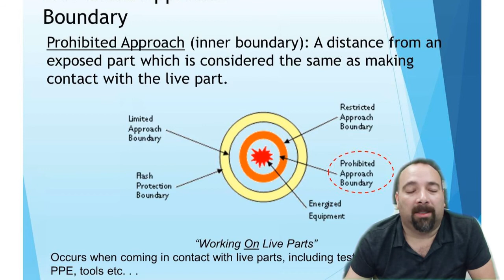We talked about labeling a minute ago. Arc flash labeling must be posted, which identifies approach boundaries and the PPE requirement. It'll tell you right on there the cal level of the suit that you need to wear, or if you just need to put on a shirt, or if you just need gloves and a face shield.